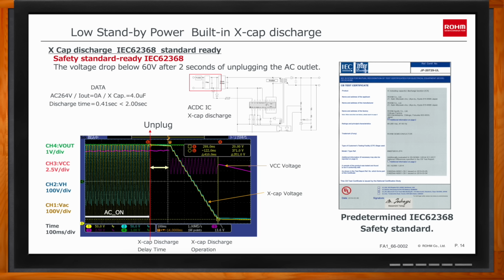That's considered the threshold for getting a shock. Without this X-cap discharge feature, when you pull the plug out of the wall, there could be as much as 130 or so volts remaining from capacitors inside the supply used to reduce EMI. Those are called X capacitors because they're connected across line to neutral on the AC input, and they could potentially hold a charge for several minutes.